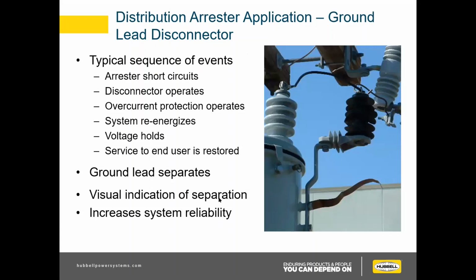So here's a typical sequence of events. As you can see in the picture here, this is a disconnected arrestor. So you have a nice visual indication of a failed arrestor. You know what happened. The ground lead is hanging down, not anywhere close to the arrestor. So this arrestor is sitting at line-to-line voltage. A couple things before I jump into the slide. Like I said, when it disconnects, this arrestor is sitting at line-to-line voltage.